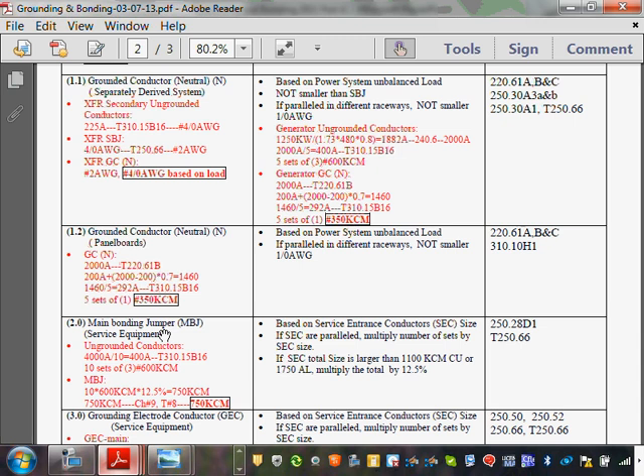If it's a wire type, most likely in a switchgear, guys, it's actually a copper bar sized by the manufacturer, UL listed, that ties the two together. So you don't even have to worry about that. But if you are to size it, this is how to size it.